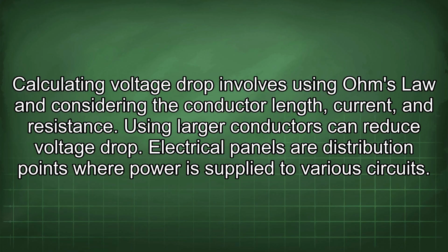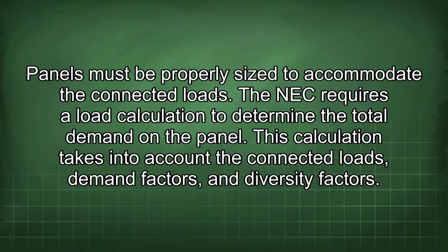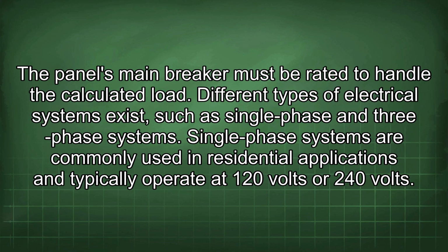Electrical panels are distribution points where power is supplied to various circuits. Panels must be properly sized to accommodate the connected loads. The NEC requires a load calculation to determine the total demand on the panel. This calculation takes into account the connected loads, demand factors, and diversity factors. The panel's main breaker must be rated to handle the calculated load.